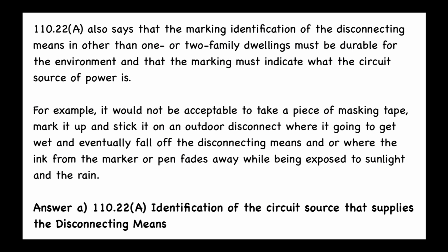For example, it would not be acceptable to take a piece of masking tape, mark it up, and stick it on an outdoor disconnect where it's going to get wet and eventually fall off, or where the ink from the marker or pen fades away while being exposed to sunlight and rain. So really, use your common sense. Put a marking, put a placard, put something on there that's going to be durable for the environment and stay there until that disconnecting means is replaced in 20, 50, 100 years, or whatever. Make sure it's going to be good for its environment.